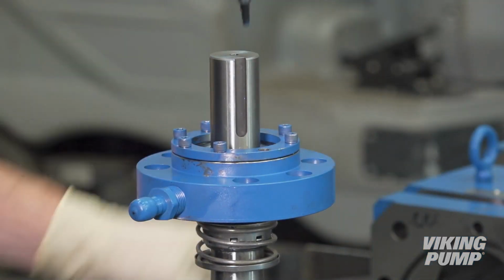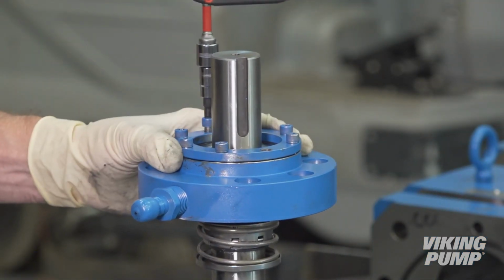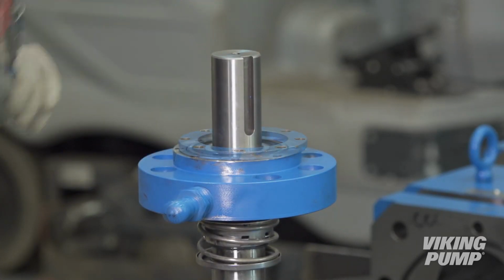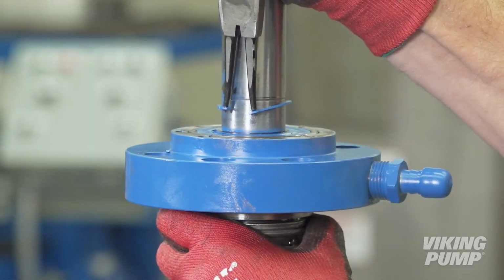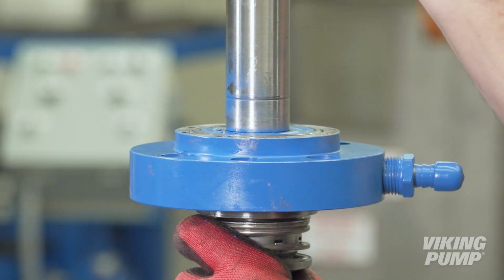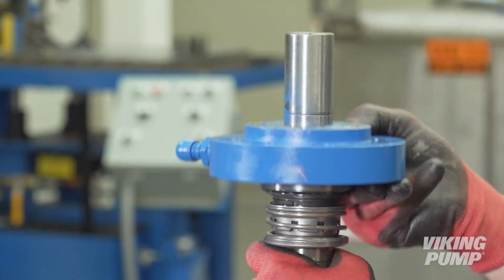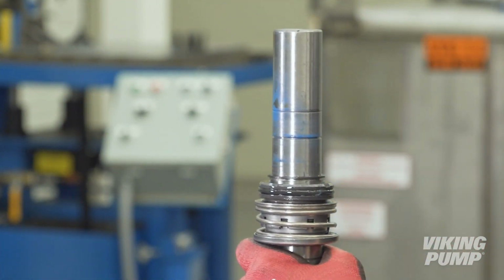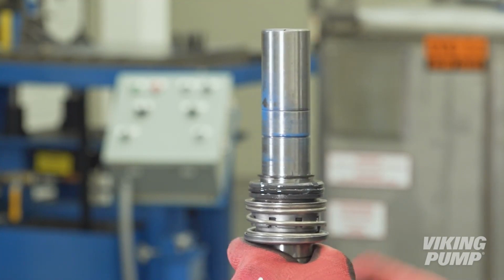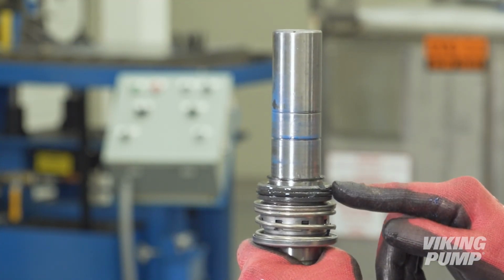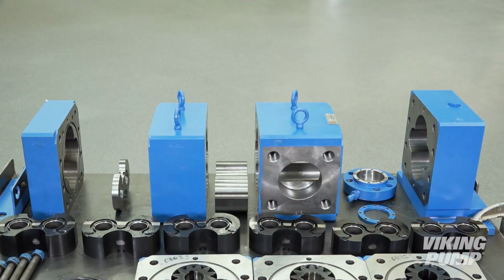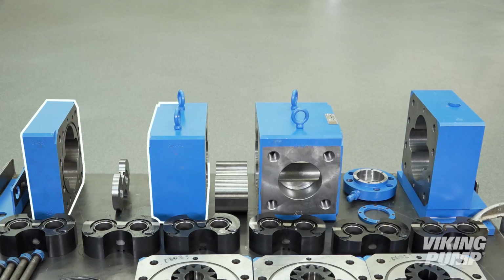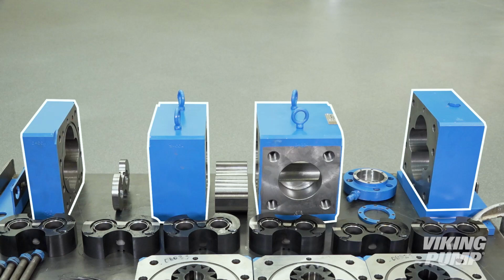Using a 3/16 inch Allen wrench, loosen and remove the bearing end cap screws. Remove the outer snap ring. Retain the seal holder assembly and bearing end cap for reassembly. You may discard the other seal components and the shaft. Prior to reassembly, ensure the pump head, separation plate, ported separation plate, and bracket are clean and free of debris.